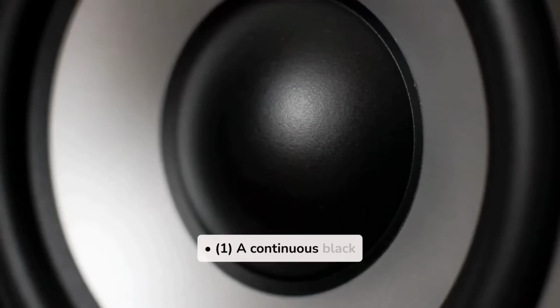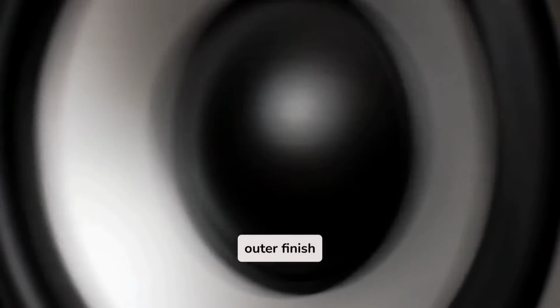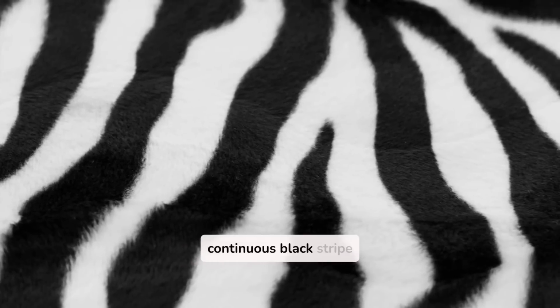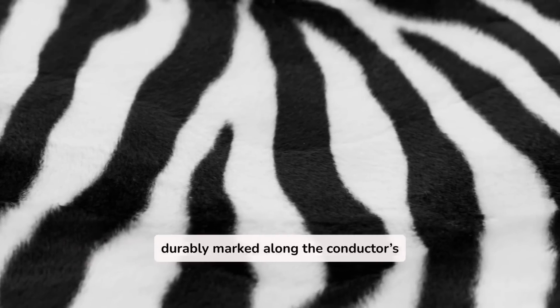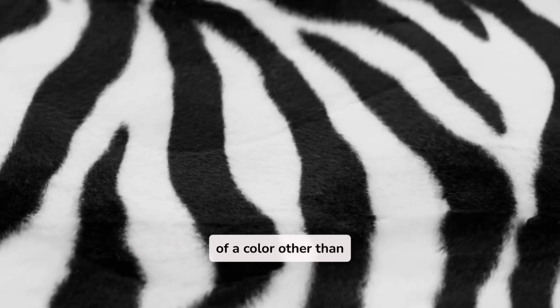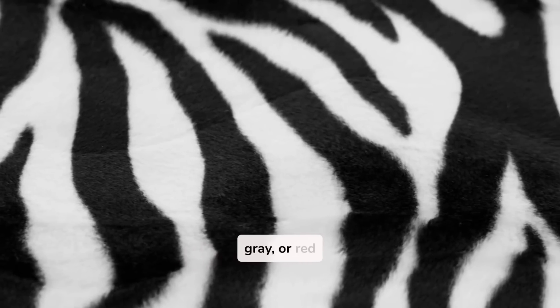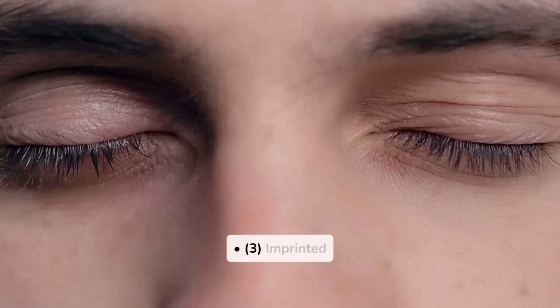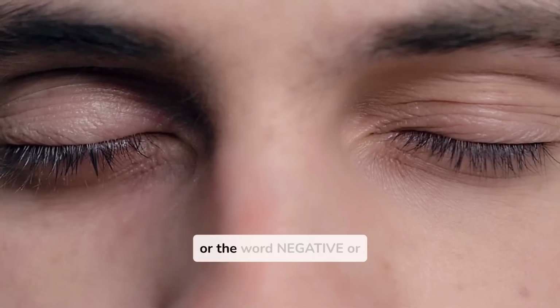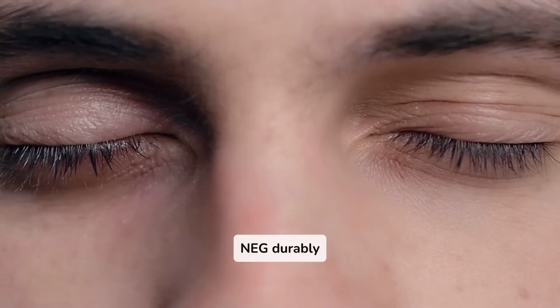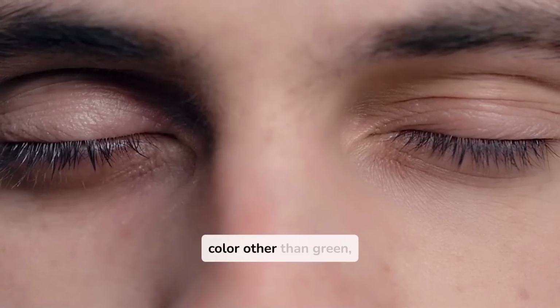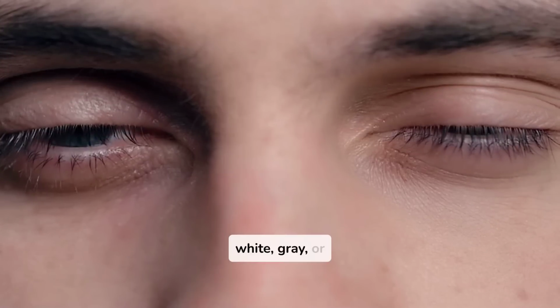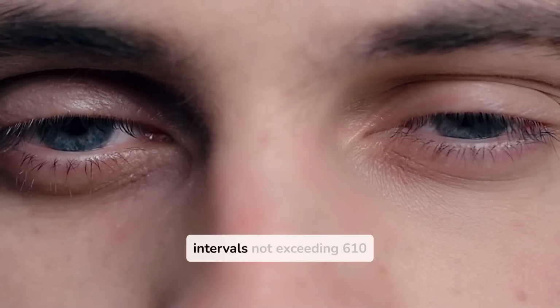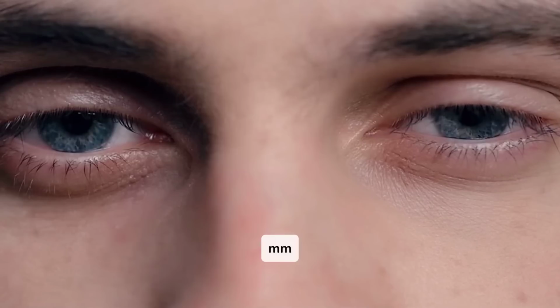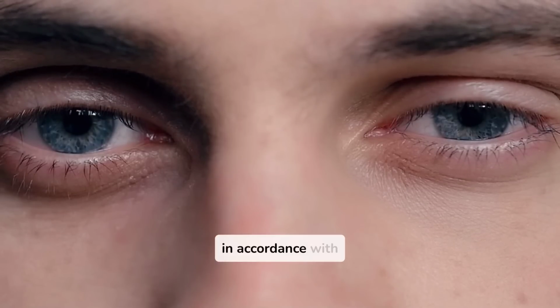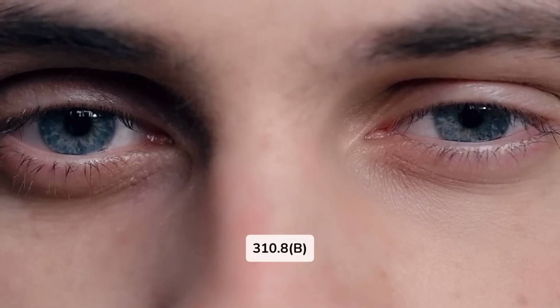1. A continuous black outer finish. 2. A continuous black stripe durably marked along the conductor's entire length on insulation of a color other than green, white, gray, or red. 3. Imprinted minus signs (-), or the word negative or NEG durably marked on insulation of a color other than green, white, gray, or red, and repeated at intervals not exceeding 610 mm (24 in.) in accordance with 310.8(B).